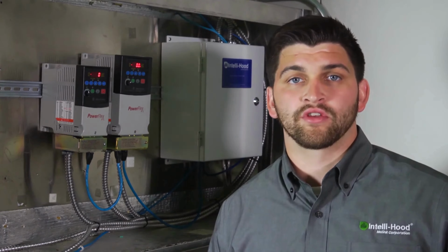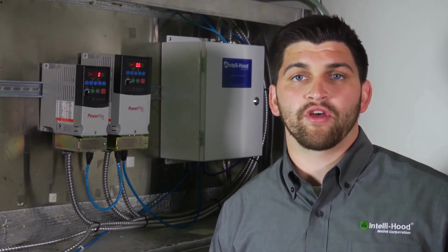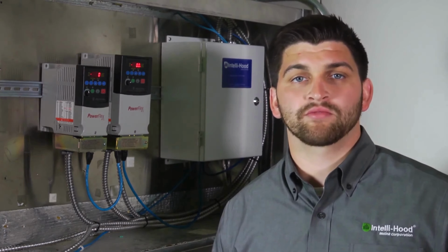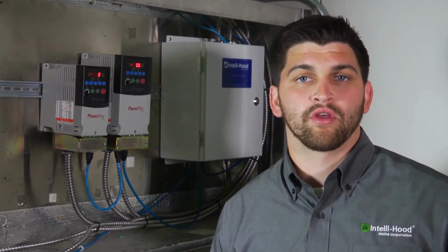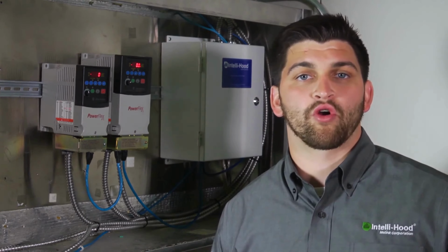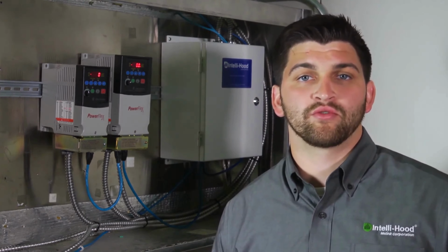For overload faults, check the motor nameplate FLA, VFD programmed FLA, and actual amp draw. If overamping occurs, reduce the maximum frequency from what is currently programmed. This would suggest that the motor is working harder either due to age, belts that are too tight, or a combination of both.